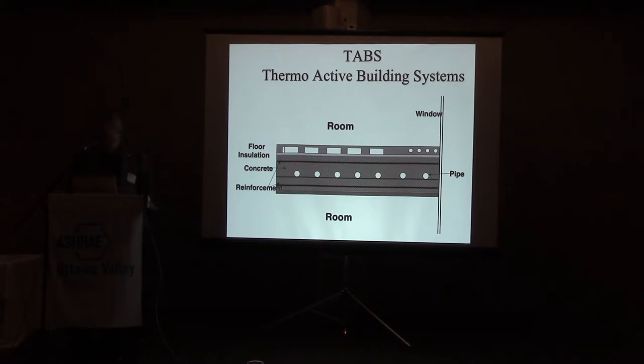Well, let me just show an example of what the idea behind such a system is, where we have a multi-story building, piping integrated between upper and lower reinforcement. You have free access to the concrete, no suspended ceiling. On the floor, you probably have acoustic insulation, and also you may have a raised floor to have cables and other things. So most of the heat exchange is assumed to be over the ceiling.